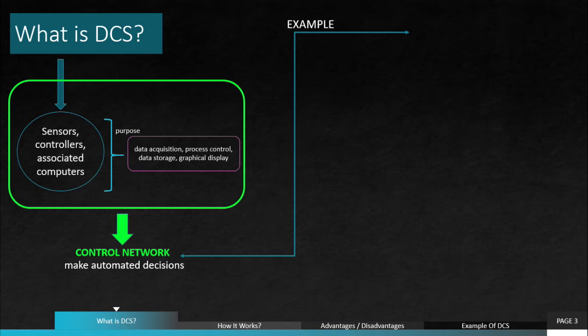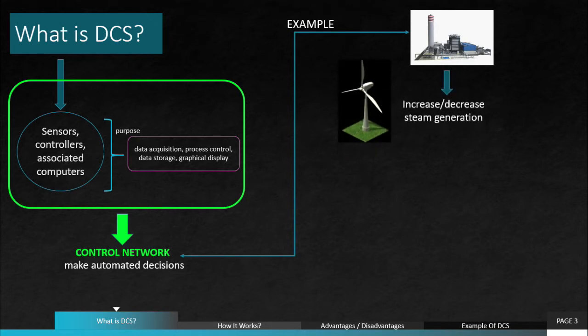As an example, the distributed control system at a power plant might automatically increase the steam generation capacity of multiple turbines in order to keep up with changing demand for electricity during hot summer days. And then it will decrease it as outdoor temperatures cool overnight and demand subsides. So in the distributed control system in the power plant, they will increase the electricity generation based on the demand. If the demand is high, then they will increase the electricity generation.